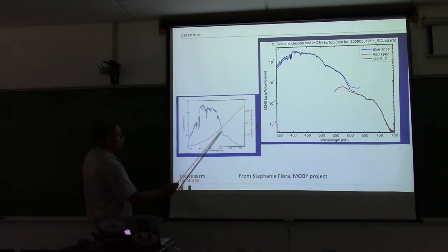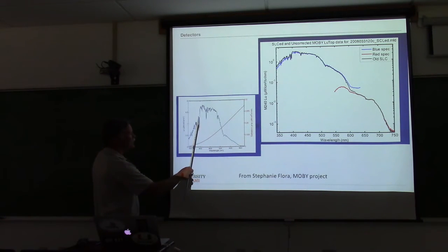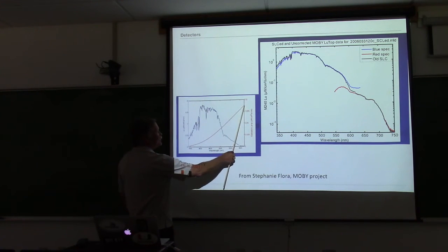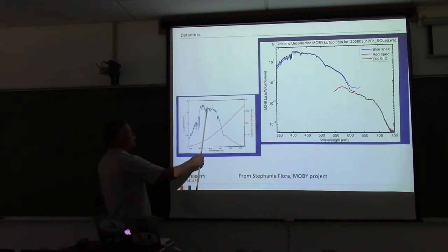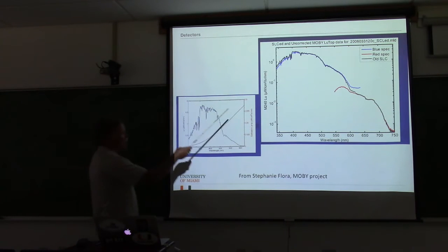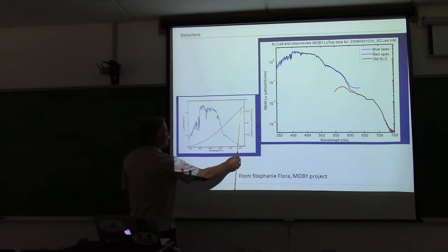This is your light field again that we're looking at. This is what a calibration lamp looks like. It's also a problem with the stray light, the out of band problem with filters: if I'm calibrating with this really red rich source and I go out in the field where I'm measuring light that's more blue rich, I'm going to get completely the wrong answer, because the stray light coming, say, at this wavelength from over here might be different in the lab than it will be in the field.